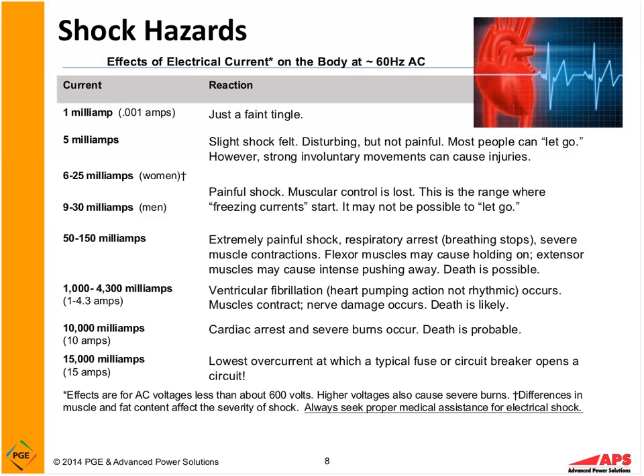By the way, the ground fault circuit interrupters that you use on temporary power cords, those little GFCIs that you've seen around your kitchen sinks, have the push to test and the reset buttons on them. Kitchen sinks, bathroom sinks, outdoors and so forth are required when doing construction type activities on project sites, and they're required in many places in residences and other locations, rooftops on commercial buildings and industrial buildings. Any place where we have water and we have electricity, those do not mix well. A typical trip threshold for a GFCI receptacle is 4 to 6 milliamps. So you can see it's still a slight shock felt, but again, it's there to trip and help prevent electrical shock that causes severe injury or death.